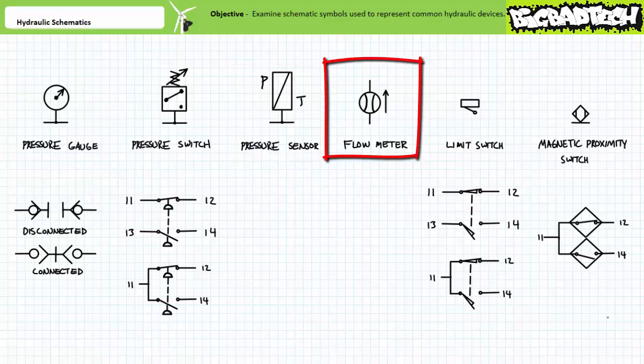The schematic symbol for a flow meter is kind of like a baseball. Flow meters are often direction and orientation dependent. A flow meter intended to be mounted vertically, in to out, won't return a proper reading if it is mounted out to in, on its side, or upside down. Flow meters that are direction and orientation dependent indicate it with an arrow off to the side.